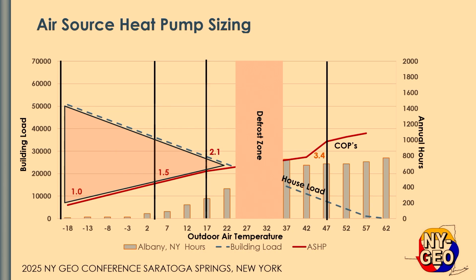And the red line is the heating capacity of the air source heat pump, and the numbers here represent the efficiency of that particular product at that particular temperature. So for instance, 47 is a pretty common temperature for an air source heat pump. That's a measurement point. We have a COP of 3.4. At 17, we got a 2.1. Here we have 1.5 at 5 degrees. And then it essentially goes to a COP of about 1, anything below that particular point there.